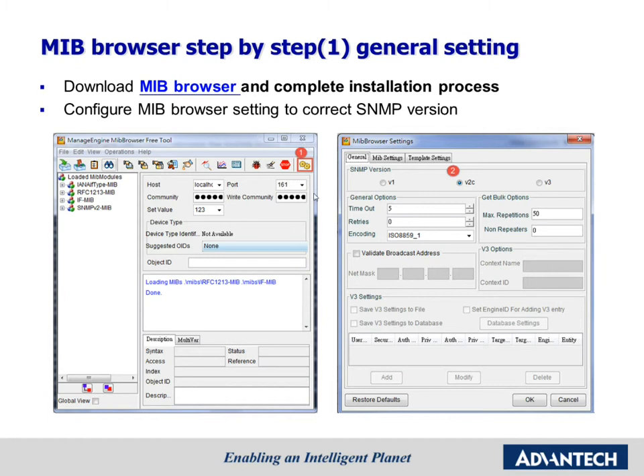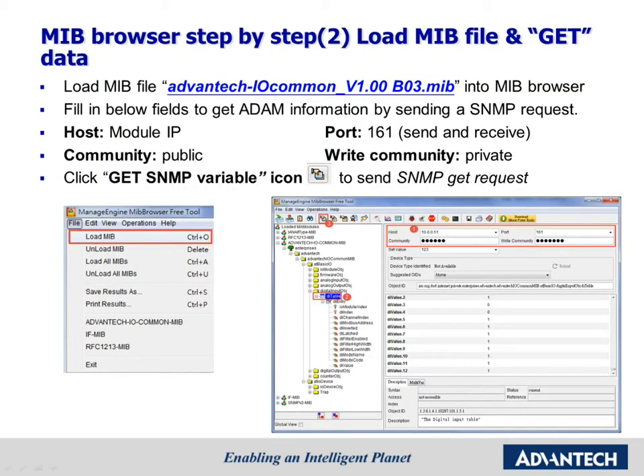First, press the gear button to configure MIB Browser settings, and then choose the SNMP version. In this example, we use v2c. Download the MIB file for the ADAM 6000 series from our website. Please note that it uses port 161 for sending and receiving. First, load the MIB file, and then enter the ADAM module's IP address in the host field. Second, choose the data you want to get. Let's send out the SNMP request by pressing the GET button. Finally, you can get lots of data from our module, like the image below shows.